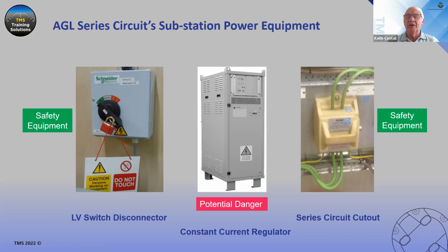And the CCR is only designed to trip out when the load goes up in the field, maybe from an open circuit. The CCR is a constant current machine. Therefore, it stabilizes the current at whatever intensity level is chosen, and it adjusts the voltage. And at a value of a load like an open circuit, where the load goes to infinity, the CCR says, oh, the load has changed, I'll just ramp up my output voltage. And at two times 4,545 volts, it's designed to trip out. But there is a time constant associated with that, so it could be much higher before it actually trips out.